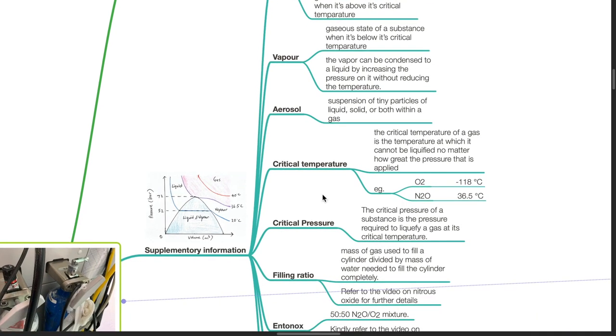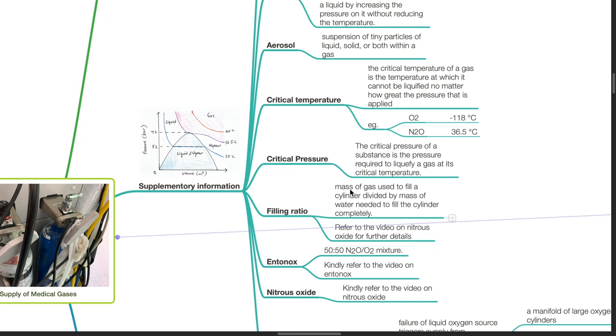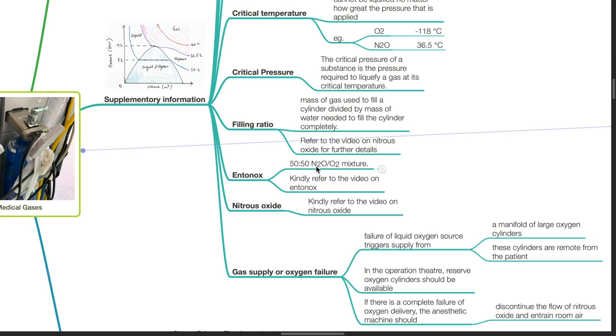Critical pressure: The critical pressure of a substance is the pressure required to liquefy a gas at its critical temperature. Filling ratio is the mass of gas used to fill a cylinder divided by mass of water needed to fill the cylinder completely. Refer to the video on nitrous oxide for further details. Entonox is a mixture of 50% nitrous oxide and 50% oxygen.